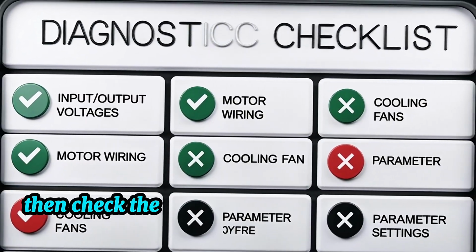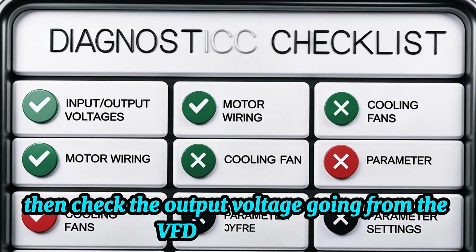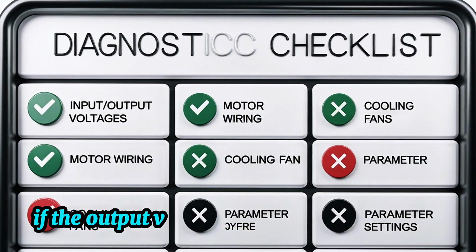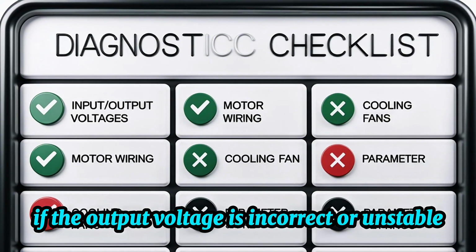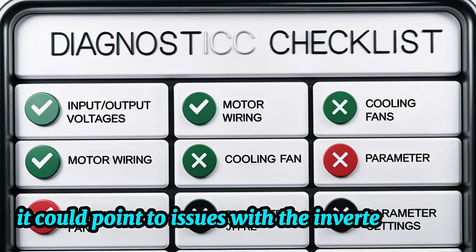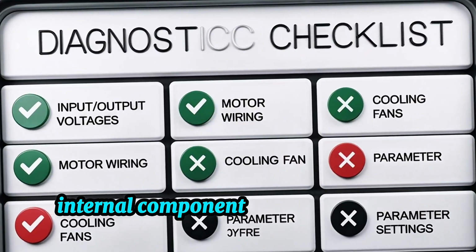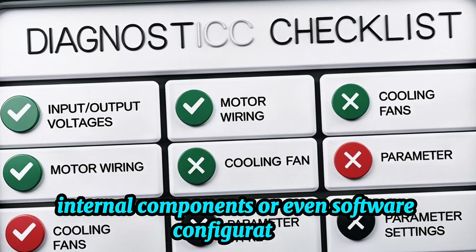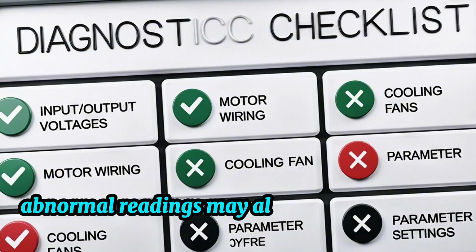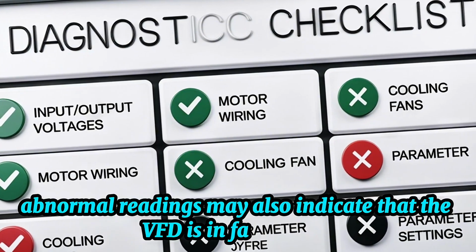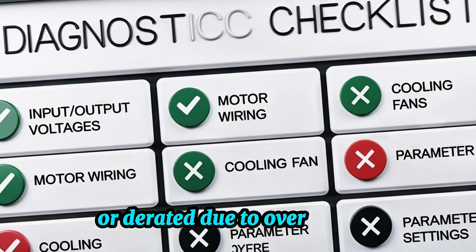Then, check the output voltage going from the VFD to the motor. If the output voltage is incorrect or unstable, it could point to issues with the inverter section, internal components, or even software configuration. Abnormal readings may also indicate that the VFD is in fault mode or derated due to overheating.